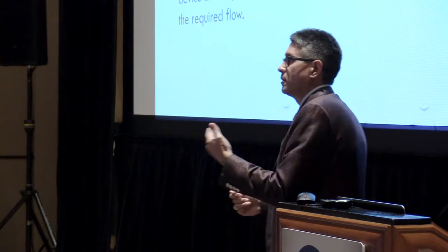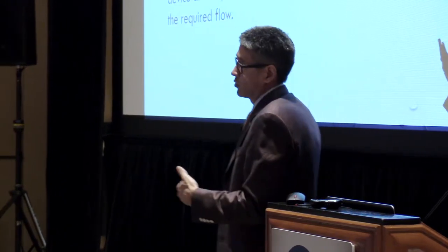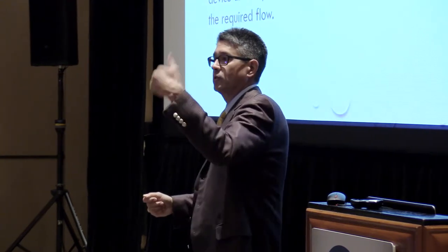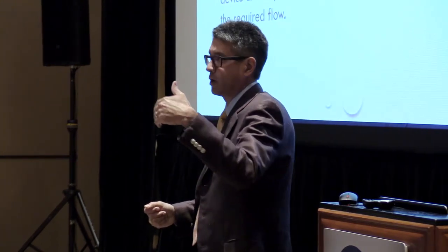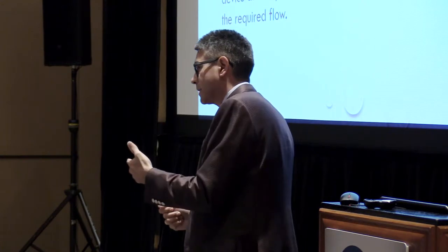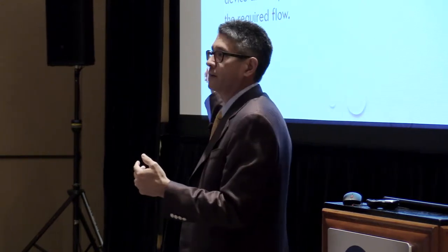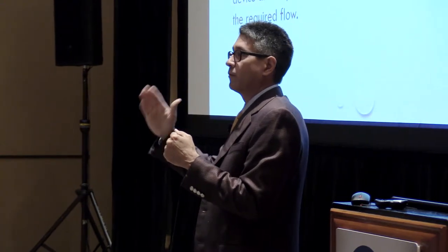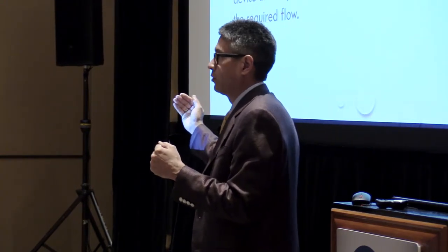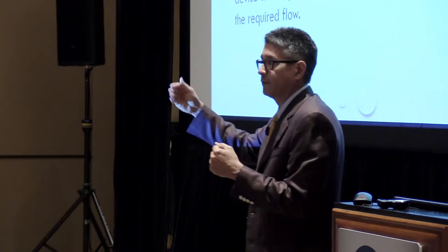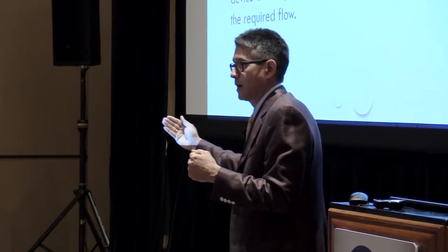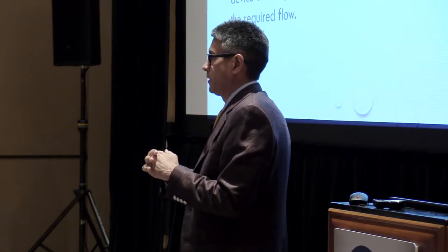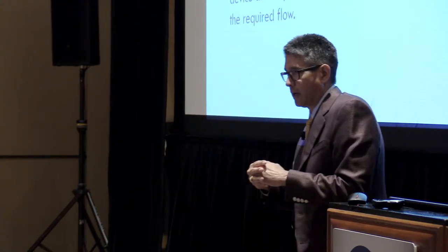To make it pressure-independent, you look at your control scenarios and say it's pressure independent because I don't care what that inlet pressure is to my control valve. I don't care what that inlet pressure is to my VAV box. All I care is that that box or that valve is going to respond to the situation and provide me the design flow or the calculated flow that's supposed to be coming out at that time. So that's the big caveat of trying to understand pressure dependent versus pressure independent.